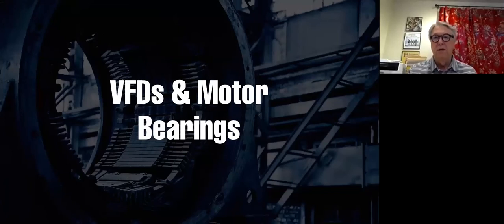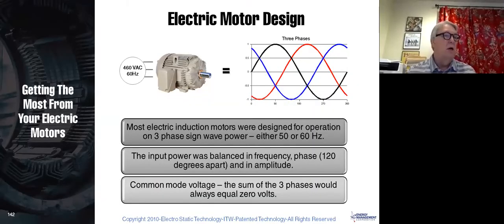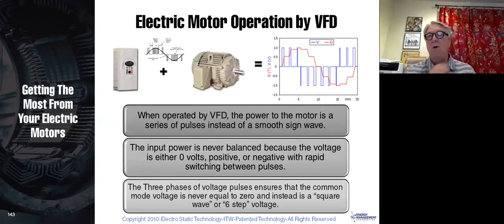Now, VFDs and motor bearings. This is very interesting. When Tesla designed the three-phase power system, he used sine waves. And when you have sine waves, then interestingly, if you add together A phase, B phase, and C phase at any moment in time, they always equal 0. And that, in theory, results in 0 common mode voltage. Common mode voltage is generally a voltage that will appear between the frame of your motor and the shaft of your motor. When you put a VFD on it, it doesn't work that way.